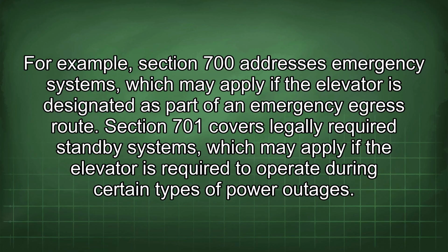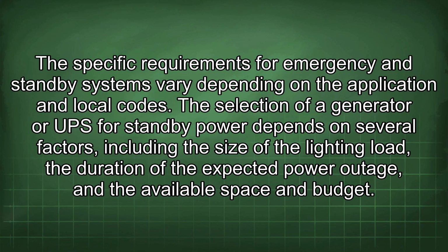Section 701 covers legally required standby systems, which may apply if the elevator is required to operate during certain types of power outages. The specific requirements for emergency and standby systems vary depending on the application and local codes. The selection of a generator or UPS for standby power depends on several factors, including the size of the lighting load, the duration of the expected power outage, and the available space and budget.